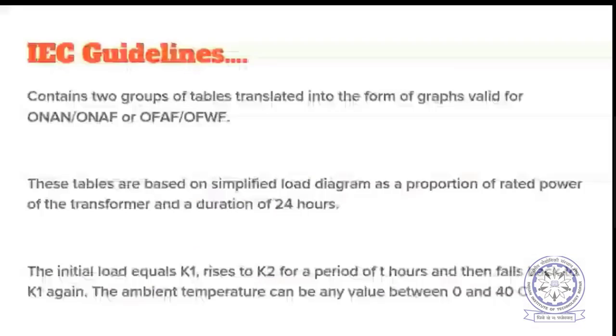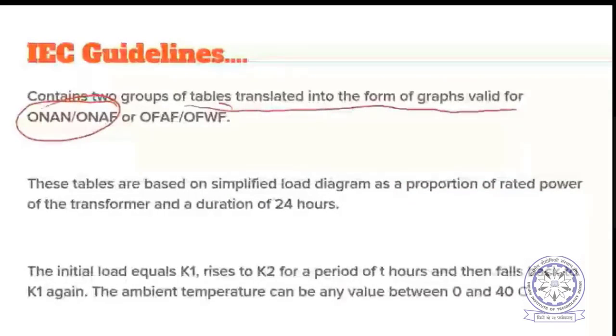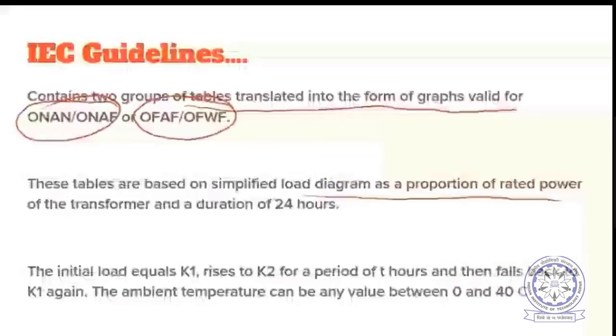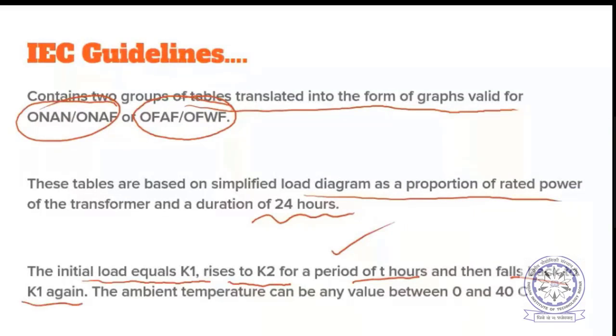And further, the IEC guidelines contain two groups of tables, translated in the form of graphs, valid for both types: ONAN, ONAF, or OFAF, OFWF types of transformers. These tables are based on a simplified load diagram, as a proportion of the rated power, for example some factor times the rated power of the transformer, for a duration of 24 hours. So the guidelines consider a load curve like this: the initial load equals K1, which is some factor of the rated power, and it rises to K2 for a certain period of T hours and then falls back to K1 again. This is what is considered in the IEC guidelines.